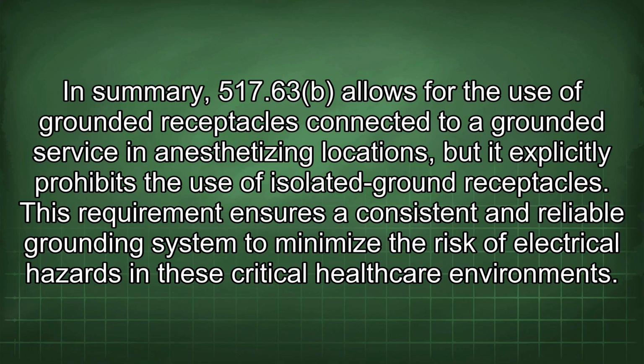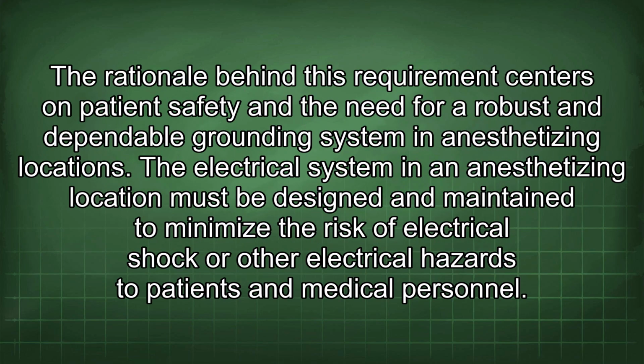In summary, 517.63 allows for the use of grounded receptacles connected to a grounded service in anesthetizing locations, but it explicitly prohibits the use of isolated ground receptacles. This requirement ensures a consistent and reliable grounding system to minimize the risk of electrical hazards in these critical healthcare environments. The rationale behind this requirement centers on patient safety and the need for a robust and dependable grounding system in anesthetizing locations.